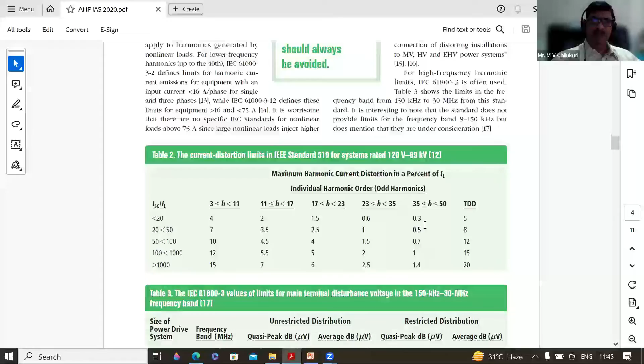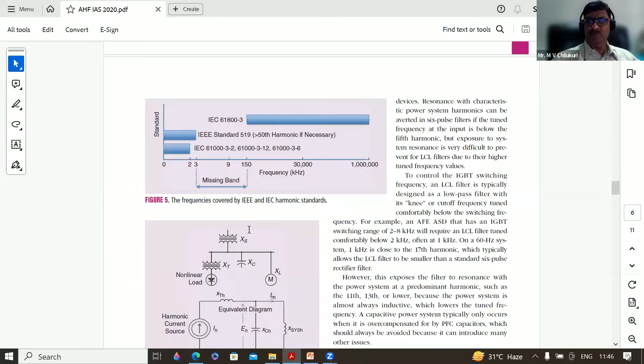Related to harmonic measurement, I want to highlight one point. IEC 61000-3-2 covers harmonic measurement up to 2 kilohertz, and IEC 61800-3 covers from 150 kilohertz to 1 megahertz. But there's a missing band in between, which is where supraharmonics come in. Both IEC and IEEE may be working on this, we don't know. From the Indian perspective, we also need to look at this band. BIS only launched the 18475 PQ monitoring standard in November 2023, and I think that needs a revision of THD calculation to address this particular band. Perhaps NFE and other organizations can take up this issue.